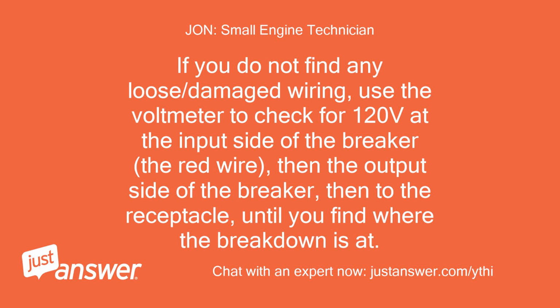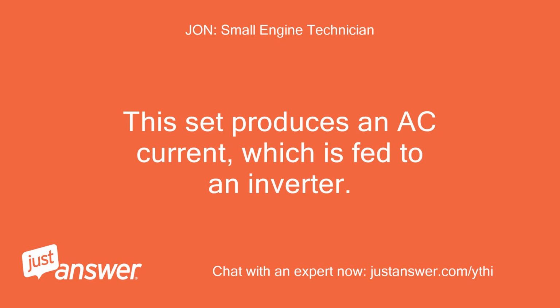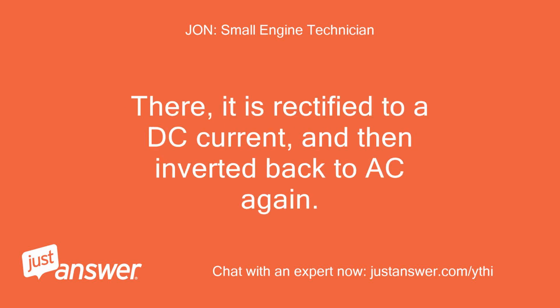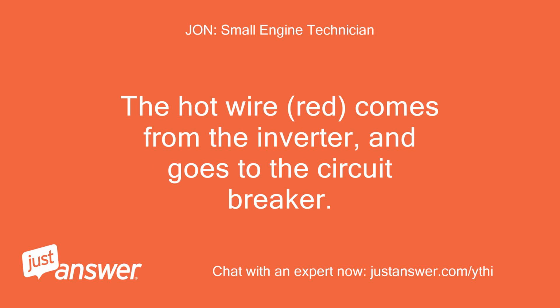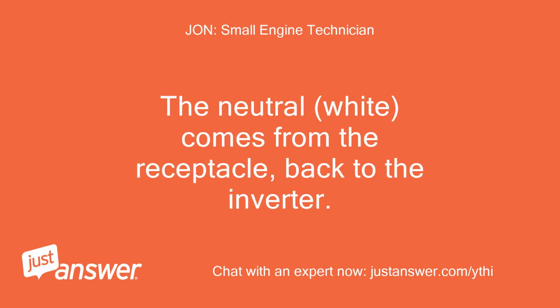If you do not find any loose/damaged wiring, use the voltmeter to check for 120 volts at the input side of the breaker, the red wire, then the output side of the breaker, then to the receptacle, until you find where the breakdown is at. This set produces an AC current, which is fed to an inverter. There, it is rectified to a DC current, and then inverted back to AC again. The hot wire, red, comes from the inverter and goes to the circuit breaker. The neutral, white, comes from the receptacle, back to the inverter.